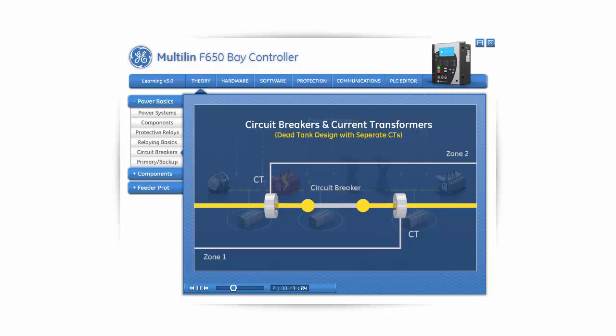The term dead tank design, when applied to breakers, means the contact enclosure is insulated from the contacts. The dead tank design typically incorporates CTs in the bushing pocket of the tank on both sides of the contacts. As indicated earlier, the protective zones should overlap to ensure that no section of the power system is left unprotected. This overlap is conveniently achieved by the placement of CTs and their connection to relays as shown.